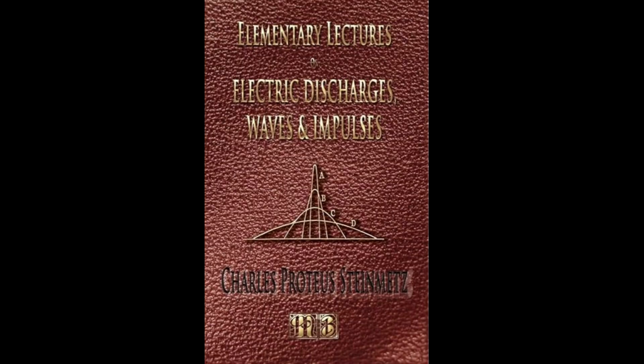The armature reaction, however, is the MMF of the armature current in its reaction on the MMF of the field exciting current. That is, that part X2 equals X0 minus X1 of the synchronous reactance which corresponds to the armature reaction is not a true reactance at all, consumes no voltage, but represents the consumption of field ampere turns by the MMF of the armature current and the corresponding change of field flux.